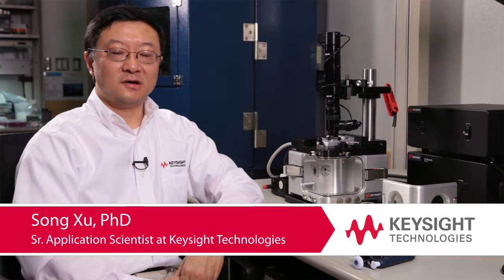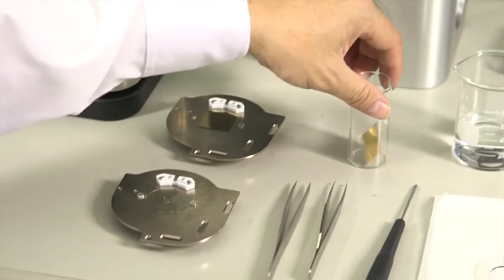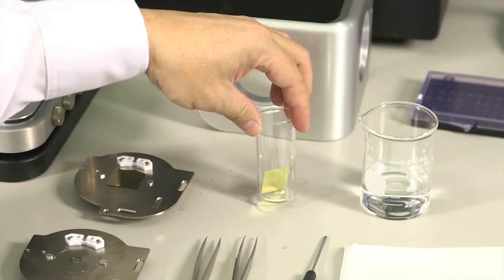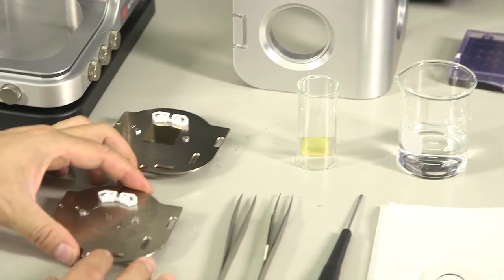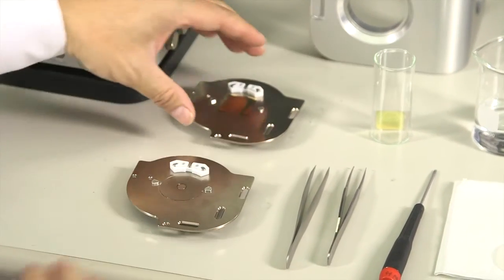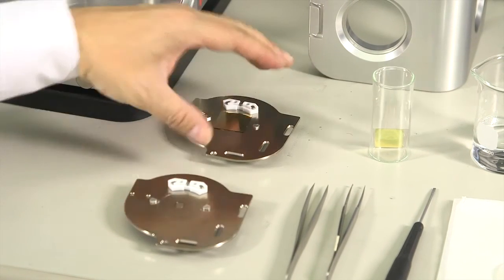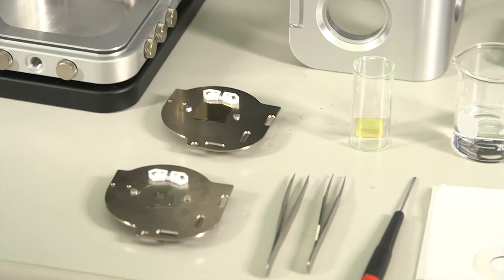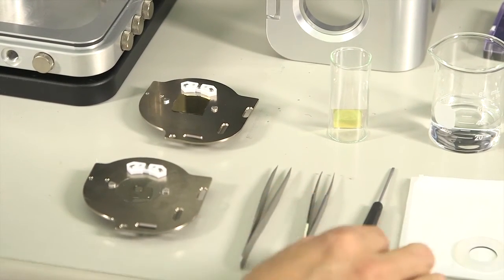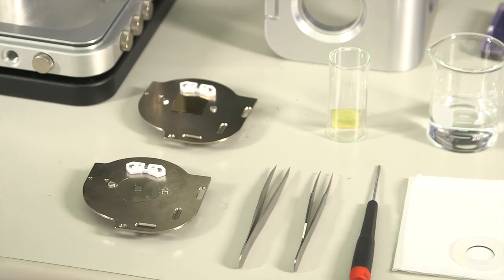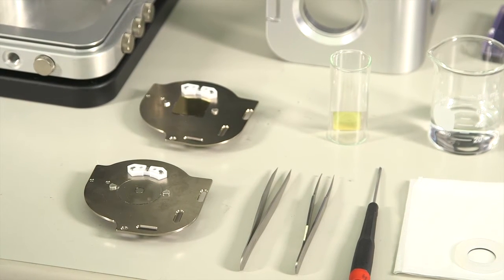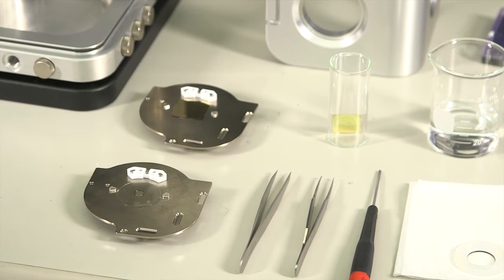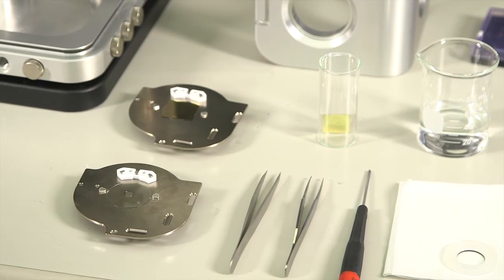In this video, we're going to show you how to do the basic setup of imaging AC mode and contact mode in liquid. We have your sample, which is this piece of gold-coated mica. We have a sample stage. We have a second sample stage for alignment. This is the liquid cell we're going to use today, and of course we need to use tweezers and a flat screwdriver. First, let me show you how to assemble the sample on the sample stage.